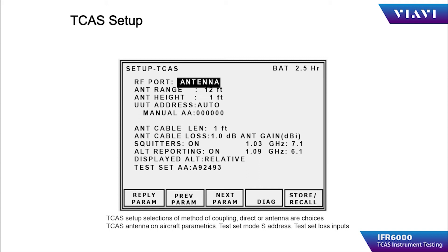Input the length and loss of the coaxial cable being used to connect the IFR 6000 flat blade antenna to the test set antenna connection. Squitters should be set to ON. Altitude reporting is set to ON. Displayed altitude is either relative or absolute; relative would be relative to the altitude of the aircraft being tested.